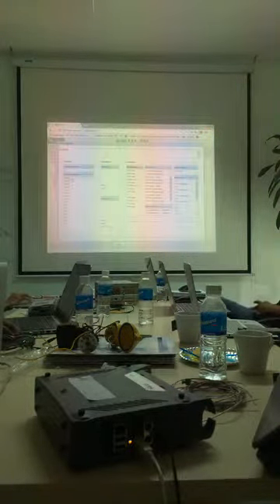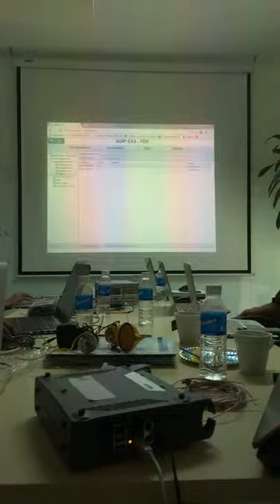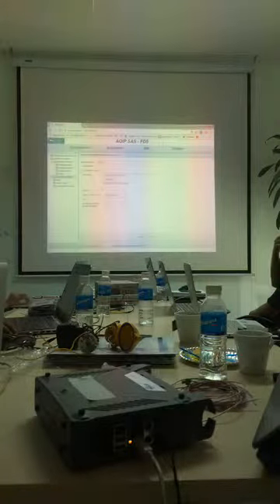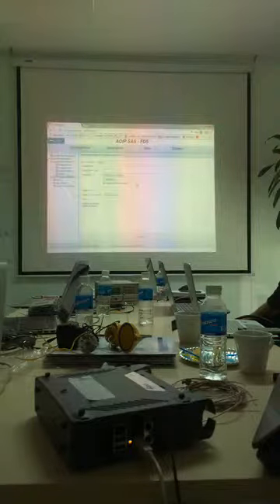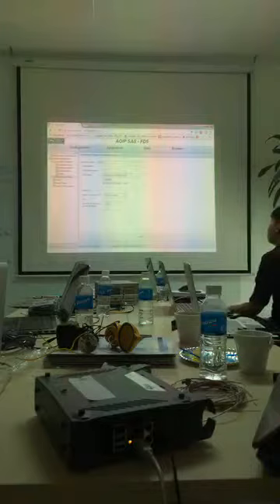That's why you start by configuring your channel. Because if you don't configure the channel, you are not able to make any calculation, and so not able to do relays. You can create calculation channels. So, for example, I want to use the value of temperature 1 and the value of temperature 2, and divide by 2. I want to see the average temperature of the two probes. For example, I want the average temperature of the room, and I put one probe on each side of the room. So that's the calculation channels.